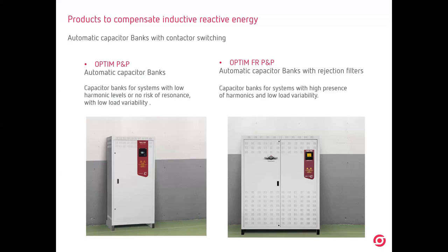In installations where we have a high presence of harmonics, we will need reactors, okay? And in installations where we don't have high values of harmonics, we will be able to install capacitor banks without reactors. But we need to measure, right? To know which kind of reactor. And also, in both cases we are connecting the capacitors by contactors. So if you have a system with low load fluctuation, low load variability, you can use contactors, because connecting or disconnecting the capacitors can take some seconds.